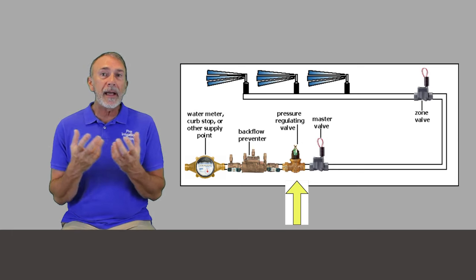If you have really high pressure, that means that the water is moving really fast when the system is on, which is a high velocity. And then when the valve shuts off, that's when you get water hammer, which is that chugging or banging sound that you hear in the system when the valve shuts off. And that can really beat apart your system, cause cracks, breaks, or cause the glue to come loose if you didn't use a good gluing procedure.